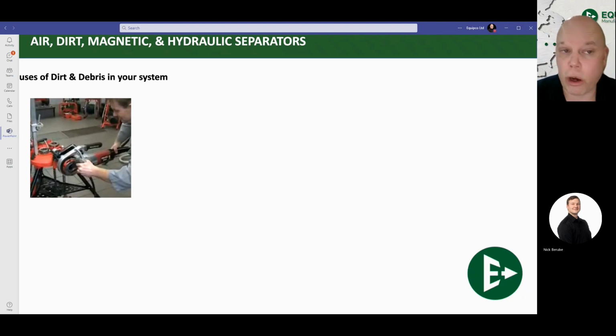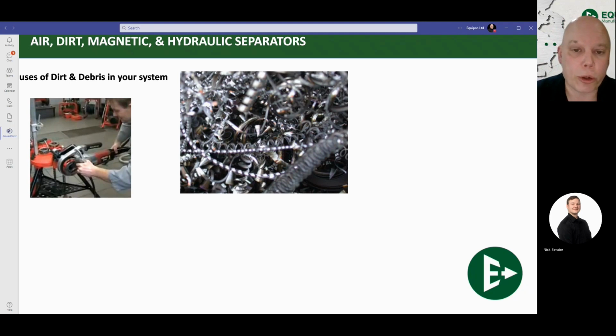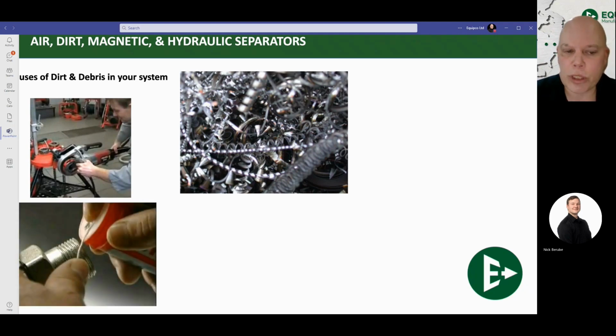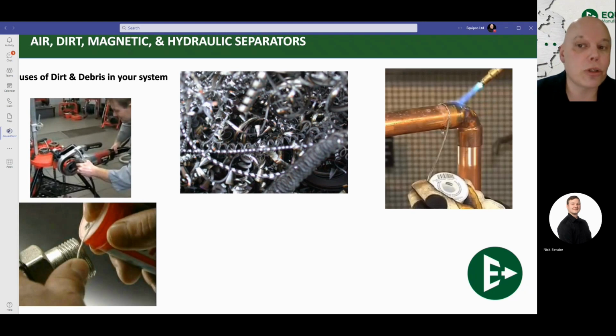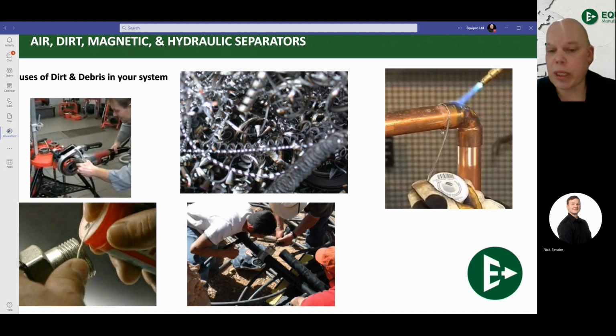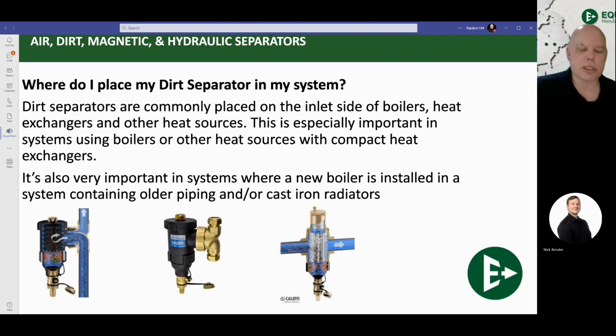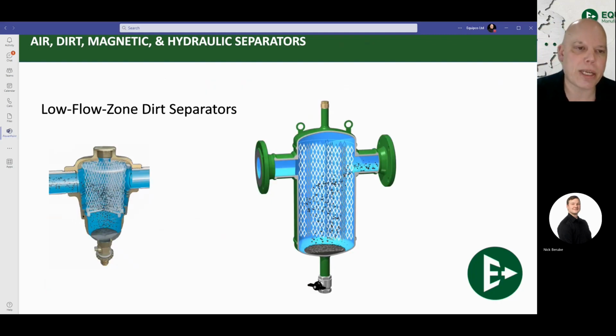So again, things you're going to see that are the cause of the dirt and debris: you have your pipe thread, your cutting oils, your metal shavings, your Teflon tapes, your flux, your solder balls, your HDPE if you're using that, plastic shavings if you're using PEX. All that stuff can build up on the inside of a system. And so you want to make sure that that stuff does not get back to the heat exchanger where it can cause problems, or back to a pump where it gets caught in the volute and can cause problems to the impeller of your pump. So we like to see it just before the boiler so it catches everything. The heat exchanger is always going to be protected.